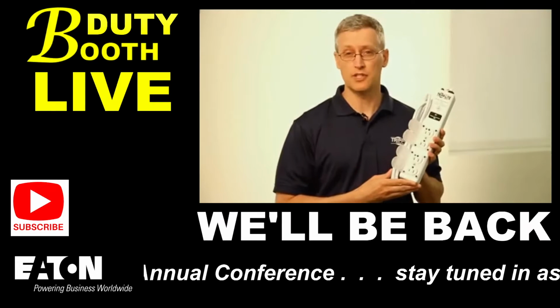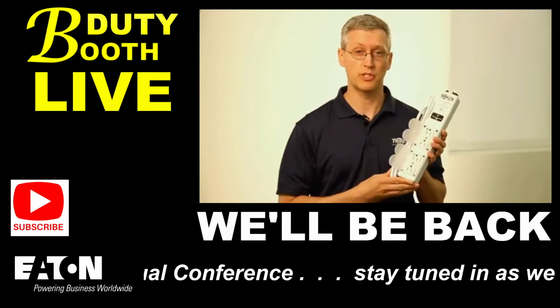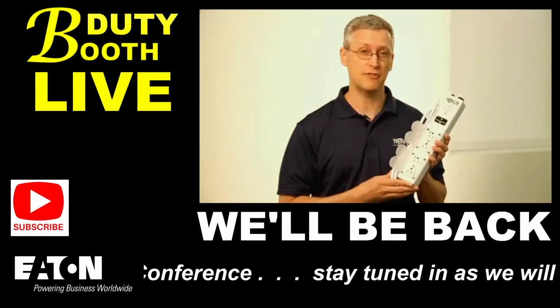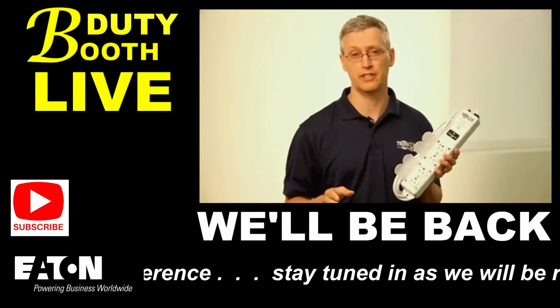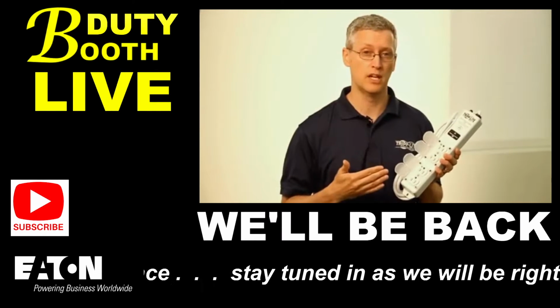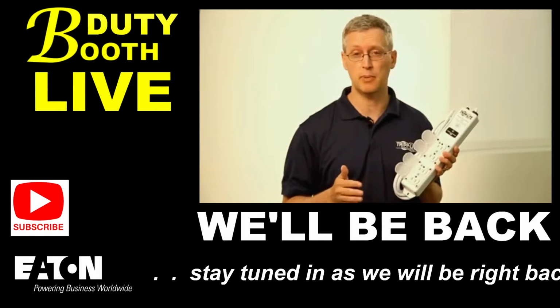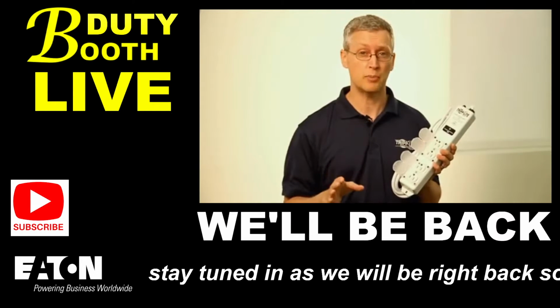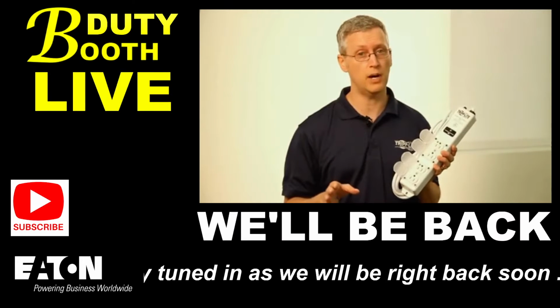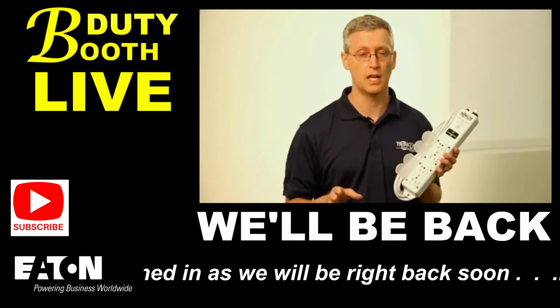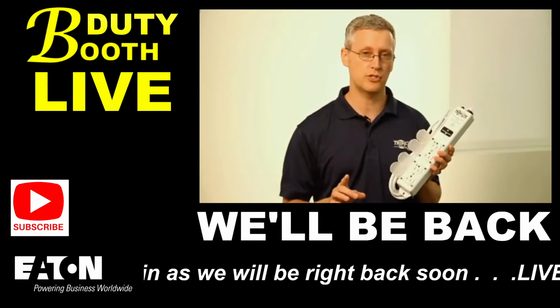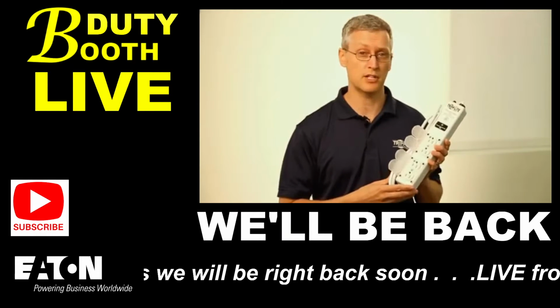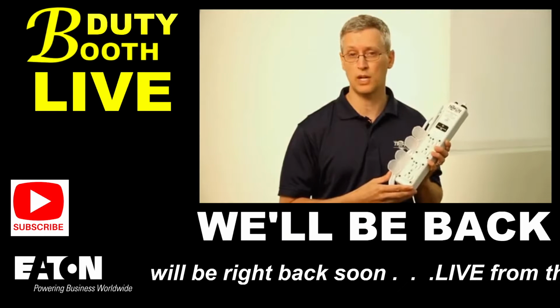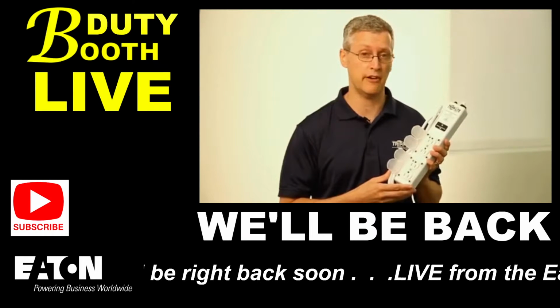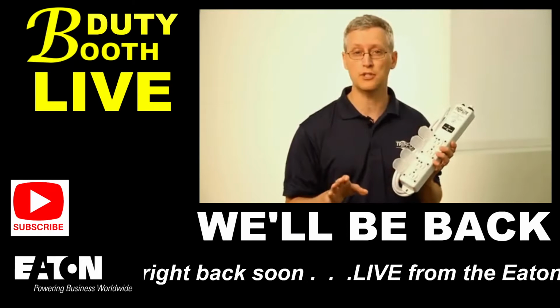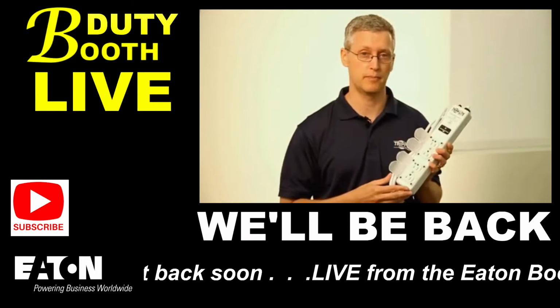Tripp Lite now offers the first medical grade power strip with surge suppression that is agency approved for use in patient care areas. It protects connected equipment from damaging surges and spikes where surge suppression on a power strip has otherwise not been available in the past. It is the first and only power strip that provides surge suppression and meets UL 60601-1 guidelines for use in patient care areas, with more features than a standard power strip.